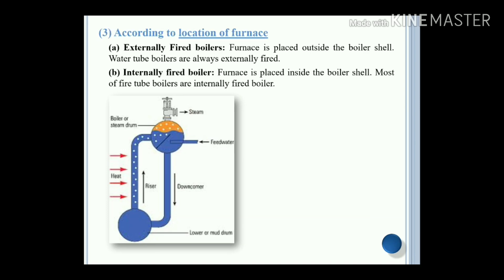According to the location of the furnace, there are two types: externally fired boilers and internally fired boilers. In the case of externally fired boilers, the furnace is placed outside the boiler shell. Water tube boilers are always externally fired boilers. In the case of internally fired boilers, the furnace is placed inside the boiler shell. Most fire tube boilers are internally fired boilers.